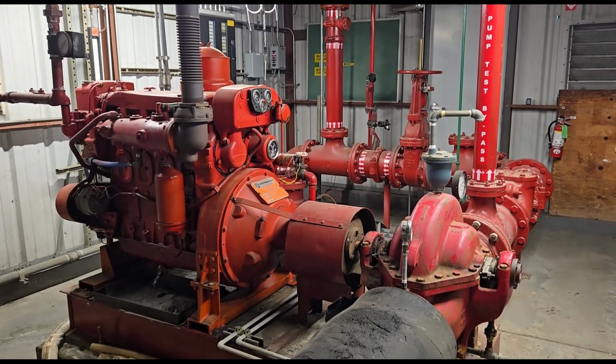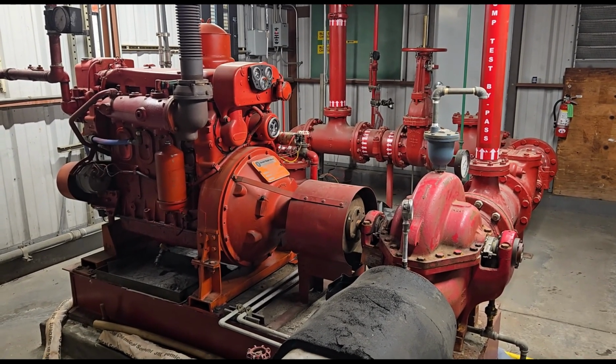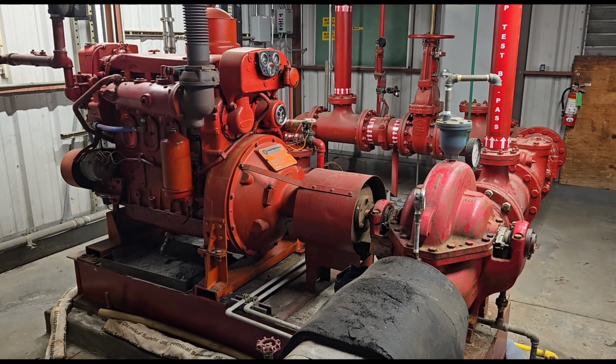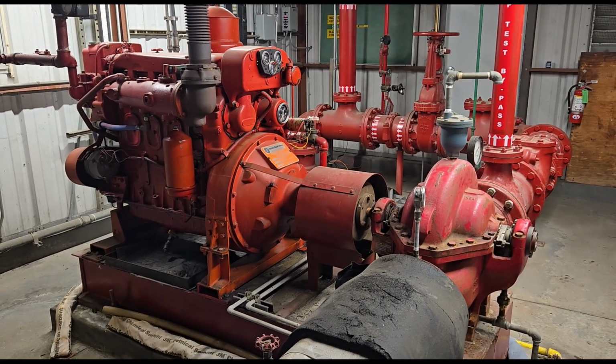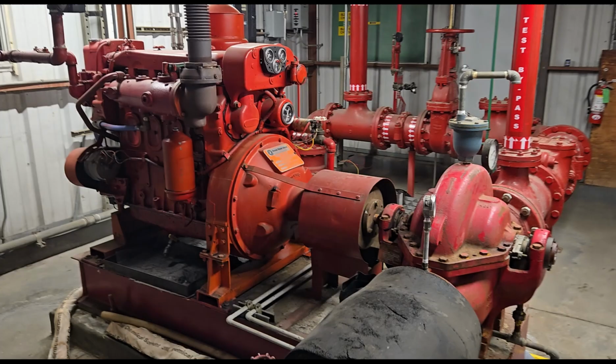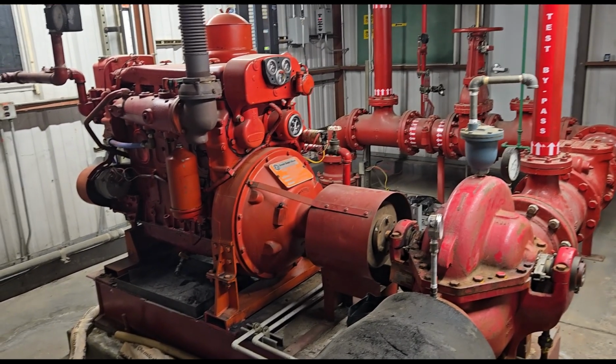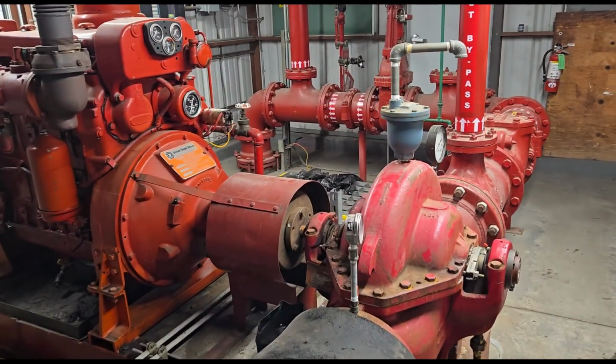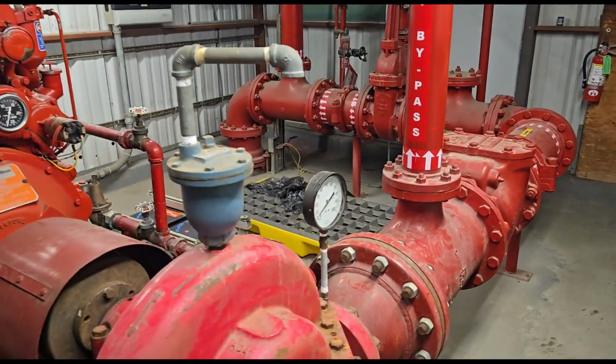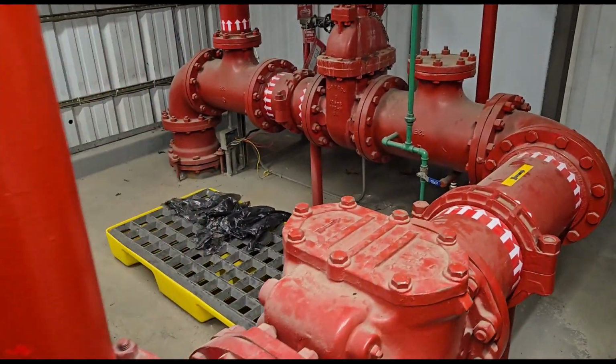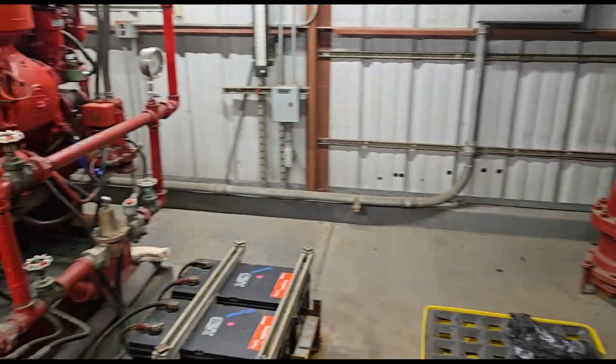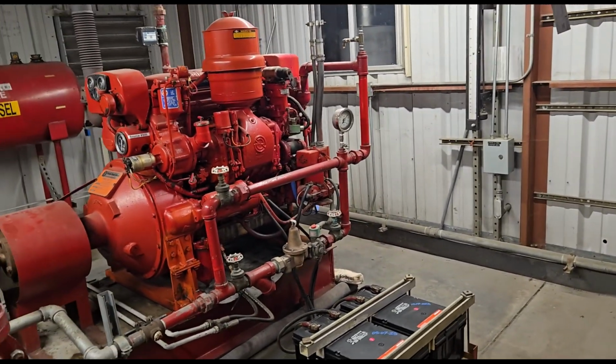So again, we're going to be bypassing this. We don't want it to activate while we're doing our flow testing. I'm doing the alarm testing for the system, so I'm testing electronics. I'm not testing the wet system, so I'm not doing the fire pump test. I'm not doing any of the sprinkler testing stuff. We have a separate team that does that. So I'm on the alarm team. I test all alarm devices. We have a sprinkler team that tests all the sprinkler devices.